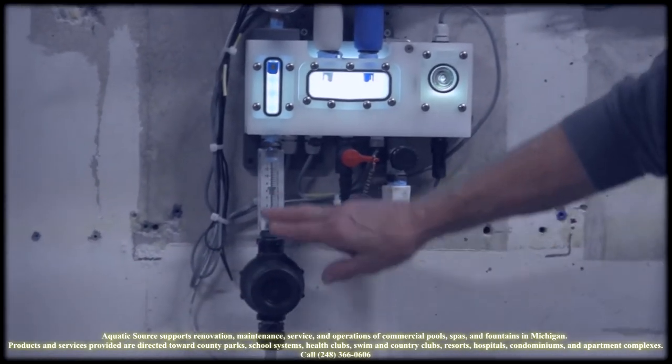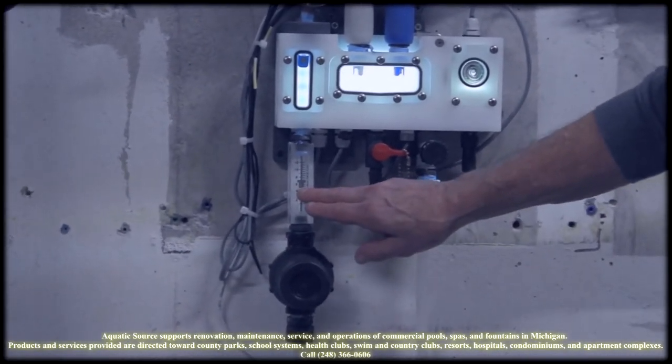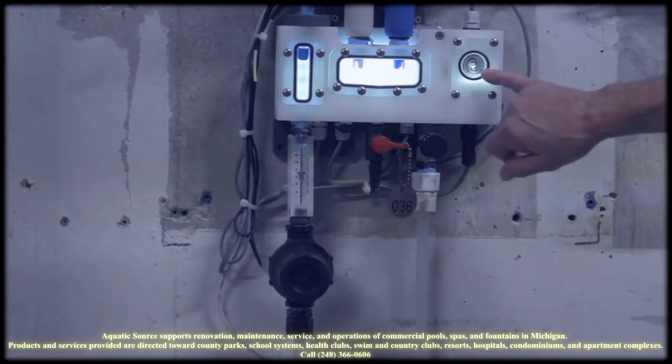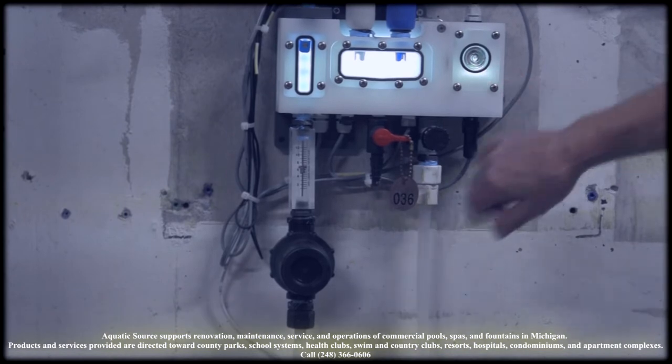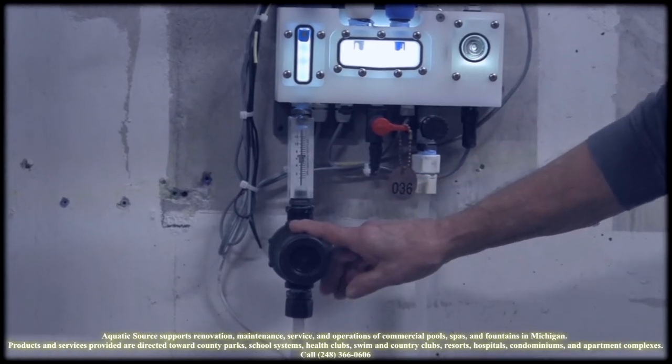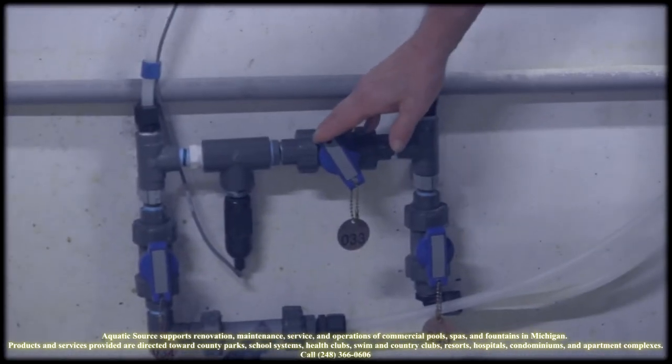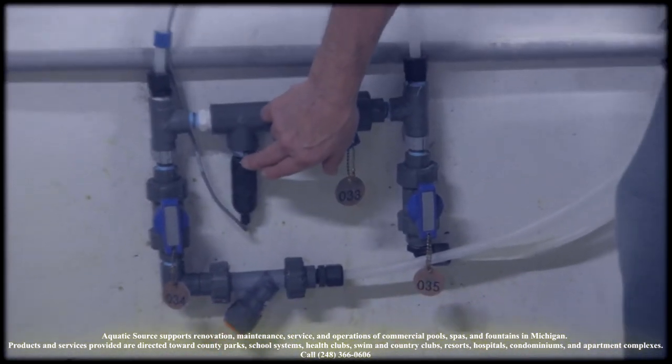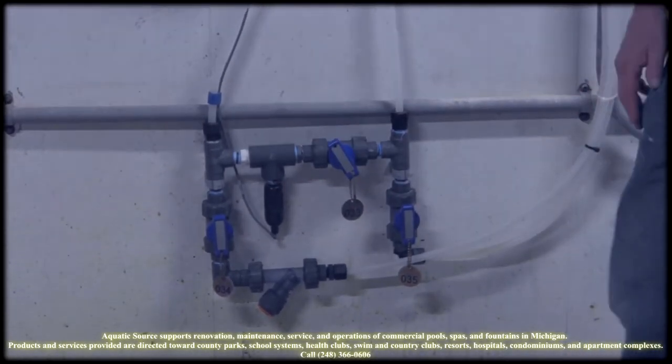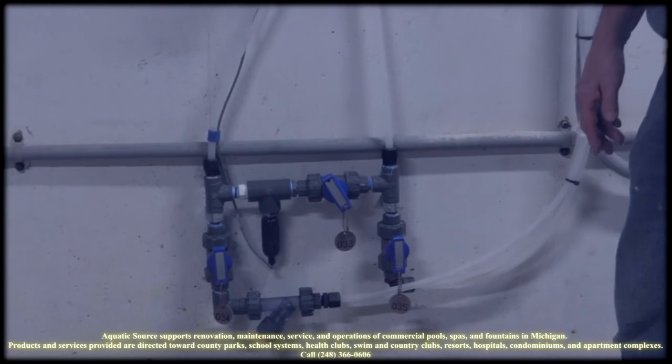We have the flow meter so that we can keep it between six to eight gallons on here, so that we don't exceed the flow rate through the CP1 probe. We have the Y strainer to prevent any debris from getting into the probe or the flow cell. We also have, in this bypass loop, a TDS sensor. It'll sense all the total dissolved solids from the chlorine or anything else in the water.